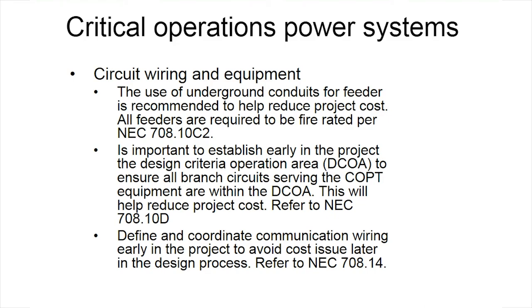Also, the design criteria operation area is important, that area is defined. COPs actually define what is the COP area on the building. So you need to go early with that AHJ and decide what area is covered by that. That is critical. You have to define it. This will definitely help reduce the cost of the project. If you define that pretty well, you will be able to reduce the cost. Make sure there are some areas that you don't have to include.